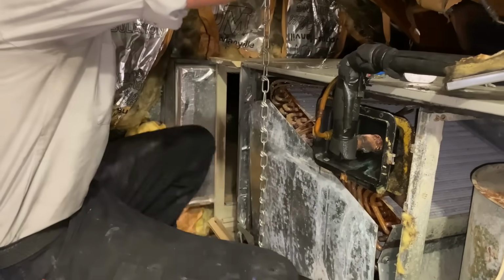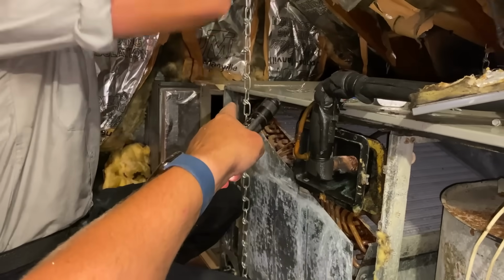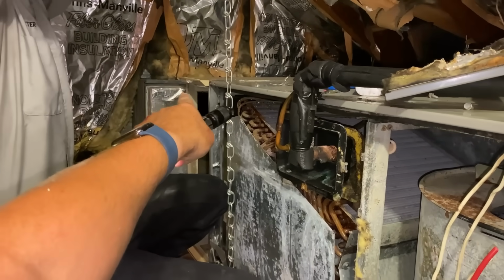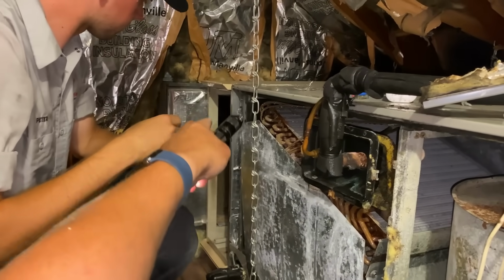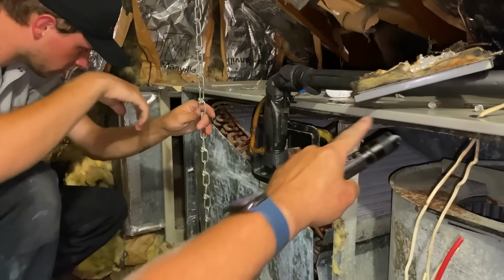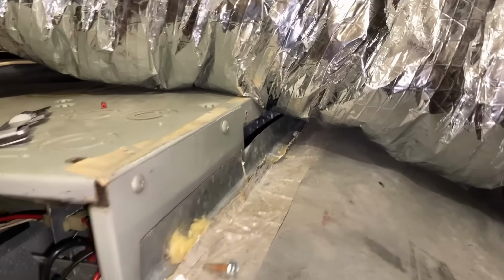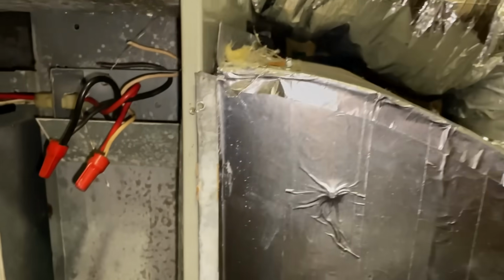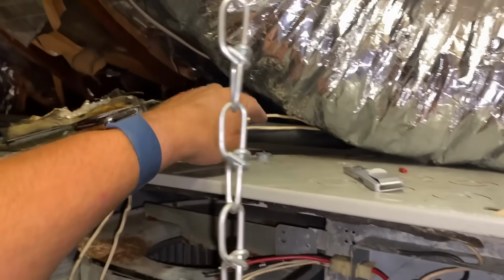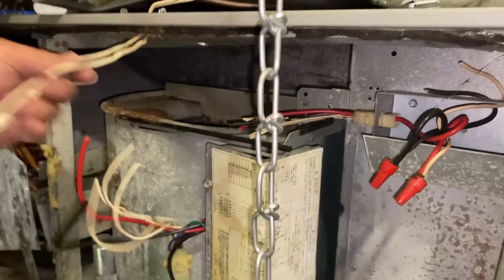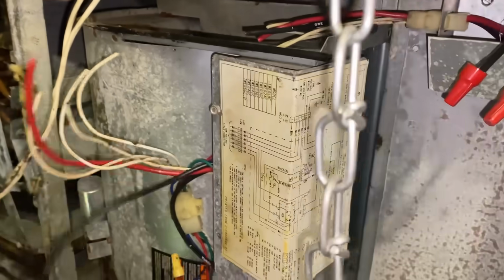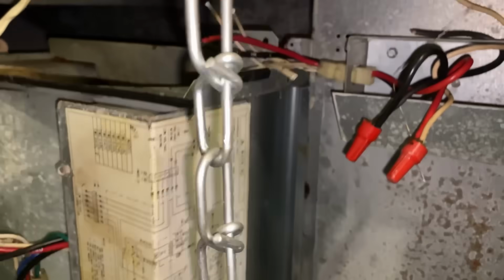All right, so starting on the return side, we pulled out all the screws that were holding in the Aprilaire media filter to the return plenum and to the air handler. Then on the supply side, we removed all the tape and screws holding on the supply plenum, even on the bottom, to the air handler. After power was shut off at the unit, we cut all the wires, then unscrewed our blower motor from the air handler itself.